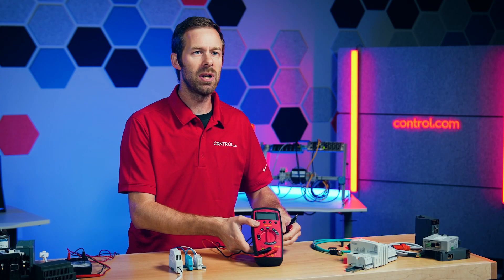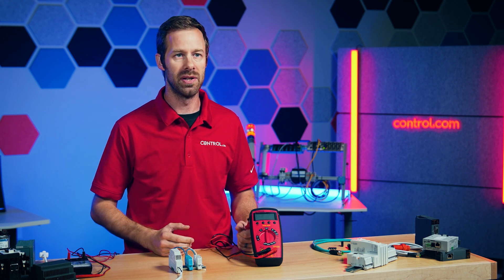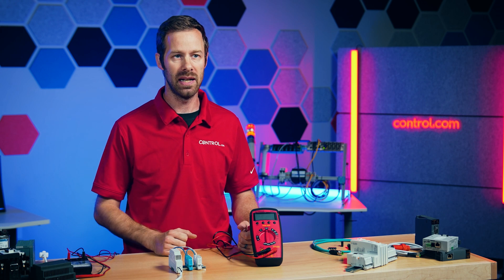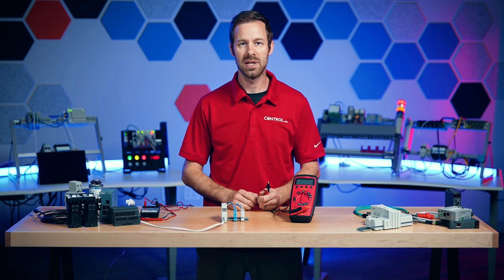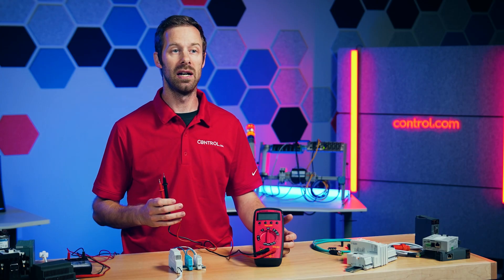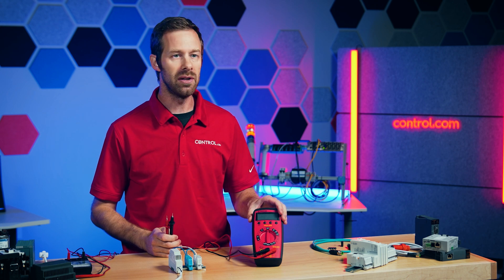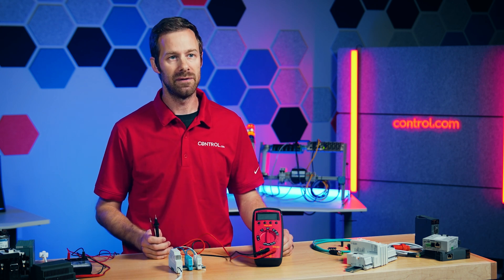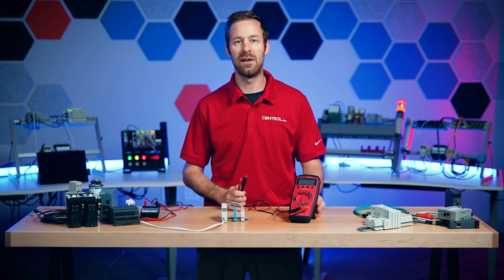So the big question is: how much does that matter? Does it really matter when we connect a voltmeter into the circuit, and do we have to be careful about how we connect it? The answer isn't as straightforward as simply yes. Most of the time, with digital multimeters — especially in industrial or control engineering contexts — the devices and the meter are so different in resistance that it doesn't really make any difference. So as long as you're using a good digital multimeter, you probably never have to worry about this.